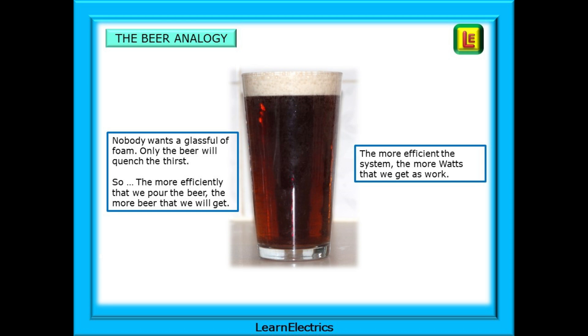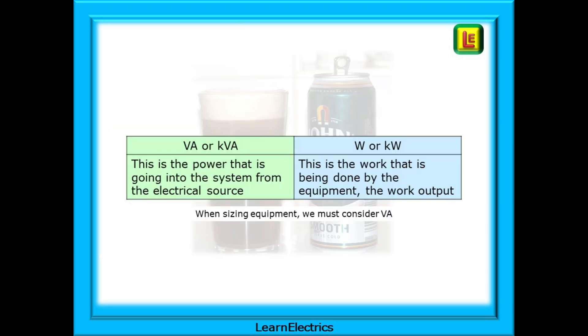Think of this electrically: the more efficient the equipment, the more watts we get to do the work. VA or kVA is the power going into the system from the electrical source; W or kW is the work being done by the equipment — the work output. Because watts will almost always be smaller than VA, we should size installations and equipment by VA. If the equipment and cabling can take the VA, then it can take the watts. And don't forget other factors affecting cable choices: temperature, grouping, insulation and so on.